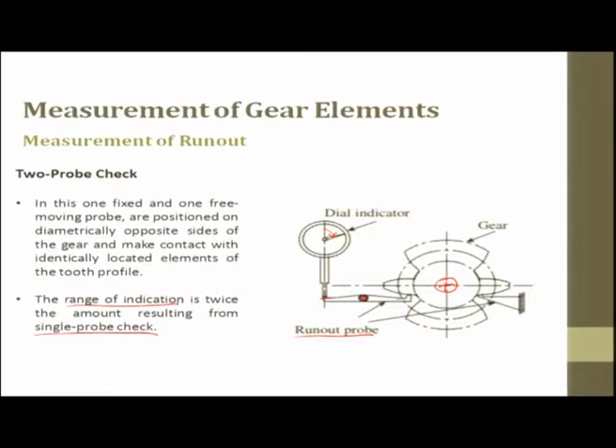When the gear comes in contact, it slides over this, and the deflections are read. In this, one fixed and one free moving probe are positioned on diametrically opposite sides of the gear and make contact with identically located elements of the tooth profile. The range of indication is twice that resulting from a single probe check, because there are two probes. The first one we saw was a single probe. Both are used to find out the runout. If there is a runout, you will not be able to transmit power efficiently.